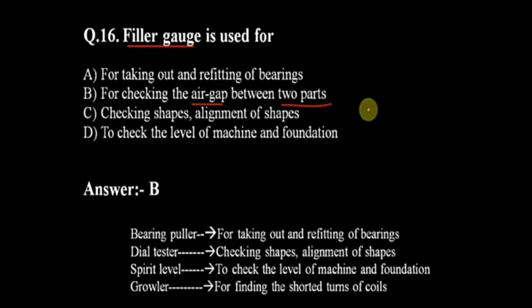Question number 16 is, feeler gauge is used for taking out and refitting of bearing, for checking the air gap between two parts, checking shafts, alignment of shafts, to check the level of machine and foundation. So our answer is option B, for checking the air gap between two parts. Feeler gauge is used for checking the air gap between two parts. So we see the function of all instruments. Bearing puller is for taking out and refitting of bearing, dial tester for checking shafts and alignment of shafts, spirit level to check the level of machine and foundation, and growler for finding the shorted turns of coil. So these are the functions of these instruments.